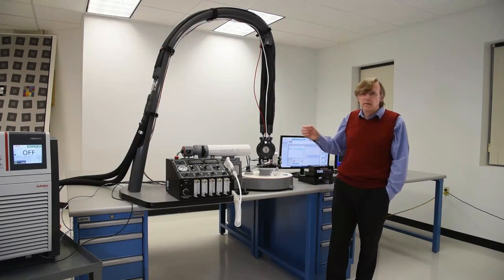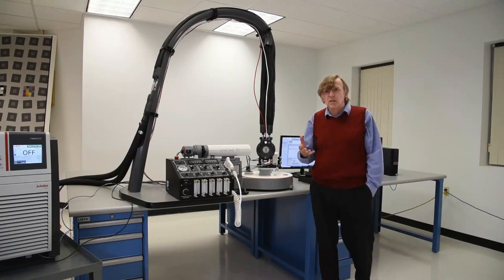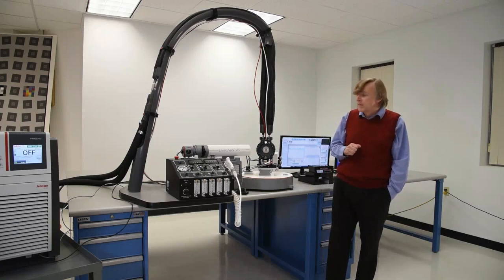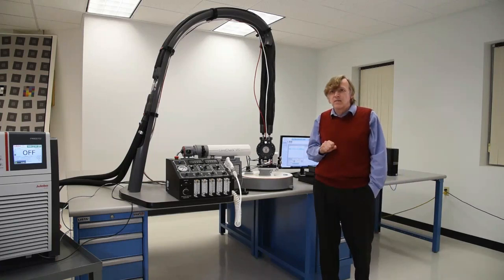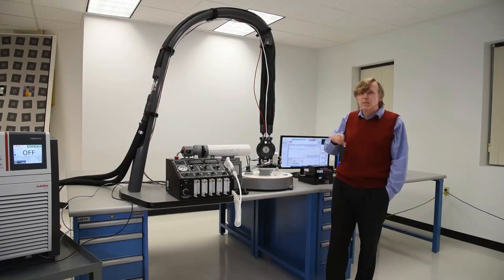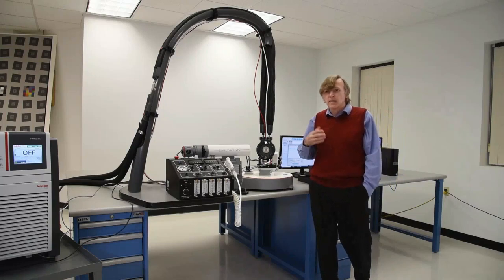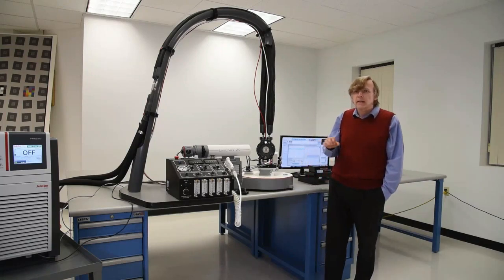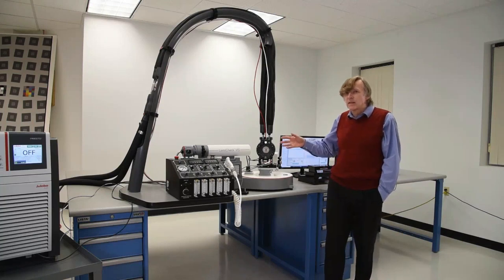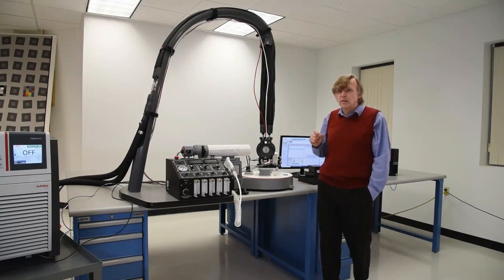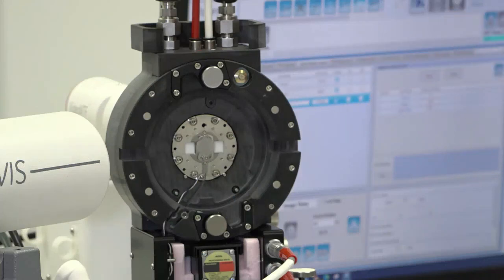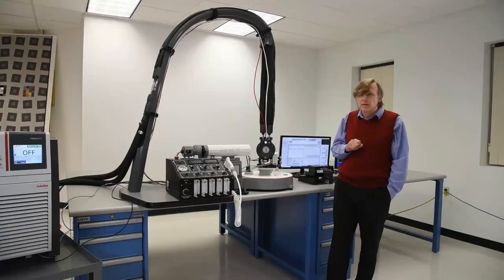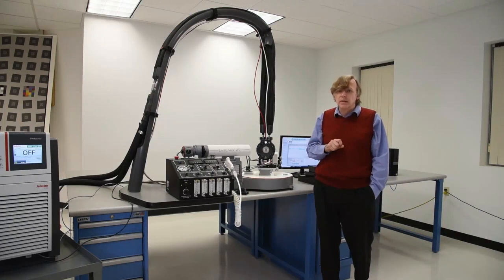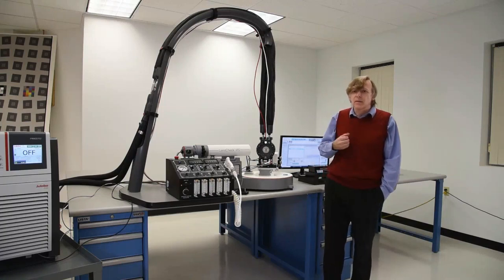We simply use the Optikos 7 software to perform a through-focus MTF measurement and then move to the plane of peak MTF. The tricky part is to find the plane of the lens flange. This has to be established at each temperature setting because it is likely to move with respect to the image analyzer coordinate system as the temperature changes. The technique we use is to build into the lens interface plate a means of holding two patterned reticles, which are these white squares, in the plane of the lens flange. I won't go into the details of how this is done, since there are several tricks that must be employed to ensure that the surrogate datum is itself athermalized.